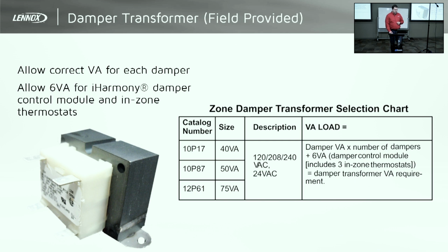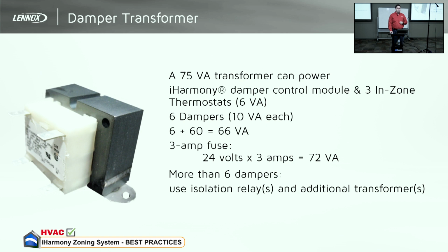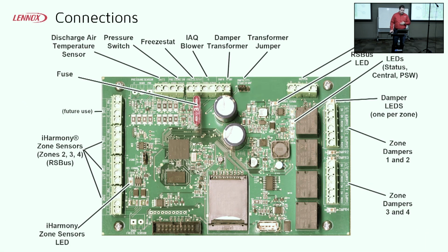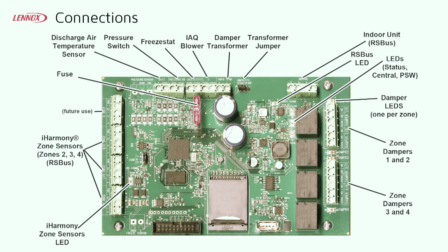Okay, we talked a little bit about sizing the zone transformer. I'll skip over that if everybody's square with that. Again, this gives us just another basic calculation on determining your damper transformer size. So this is what the zone board looks like as far as the terminal connections and whatnot. On the right-hand side here, you've got your damper connections.